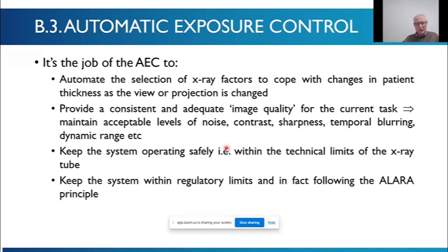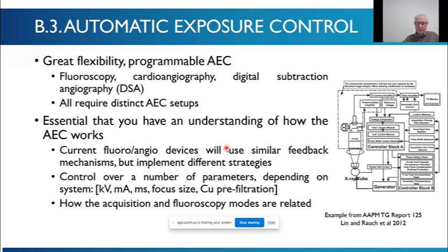So it's a very important component of the imaging system. It's crucial, actually. It plays a huge role in determining the dose and image quality balance. They're very flexible, as Annalisa showed earlier on. These fluoro or dynamic systems can be used for a great range of tasks, and this AEC is programmed to switch parameters and settings for the different tasks. It can be doing fluoroscopy, some cardioangiography, DSA at a certain frame rate, and they all require different programming in terms of how the X-ray factors are selected as patient thickness changes. And it's really important that you have some idea of how the AEC works on your system. It will be different between different manufacturers and between different types of system. It could be simpler on small mobile C-arms, for example, than on large interventional suites.